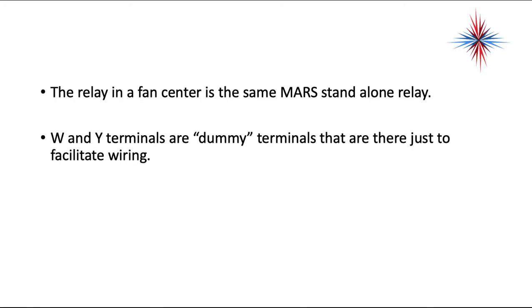The relay in the fan center is the same as a Mars standalone relay. If that relay goes bad, just pop it out and replace it with a standard Mars relay. The W and the Y terminals are dummy terminals that are just there to facilitate wiring. It's a lot neater to put your wire junctions under a screw than a whole bunch of wire nuts around the place.